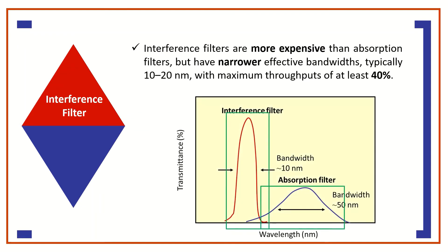Interference filters are more expensive than absorption filters but have a narrower effective bandwidth, typically 10 to 20 nanometers, with maximum throughput of at least 40%.